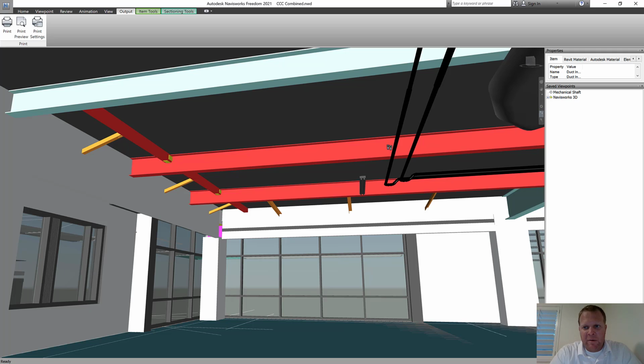But at some point in time I'd probably switch that mentality and go, no, I do want to be live, I do want to protect the entire building. So if we're tested out to some degree and have fire alarm monitoring as well, and that was all going, I would definitely go live, even though we might not have the entire building signed off by certificate of occupancy. If enough work was done in the place, I would protect the building.